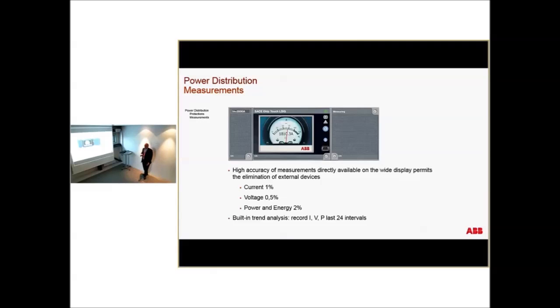Measurements, again: in some cases you need professional measurements, something like 1% of energy. But with a breaker it's still not possible. We are working on that, but it's still not possible. Now the best we achieve is 2% on the power and on the energy, 1% on the current, and 0.5% on the voltage. Again, if you don't need a very professional, class 1 energy meter, you can use these measurement systems here. Again, no additional cabling, it is already built inside the breaker.